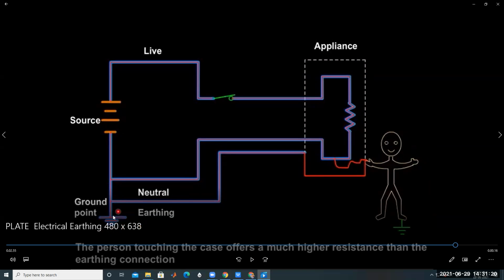If the resistance of the plate earthing or pipe earthing is very low, the fault current or leakage current passes through the earthing. The human body also offers a path, but its resistance is higher compared to the earthing, so the current always chooses the low resistance path. So no current passes through the human body under proper earthing conditions. The current is diverted and passes through the grounding. In this way the protection can be done. This is about plate earthing.